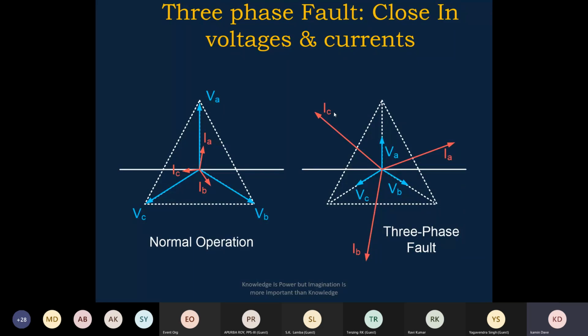Negative and zero sequence is less than 20%, and phase current is higher than 1.2 times or 1.5 times, and the voltage is less than this, then it is considered a fault condition, not a load condition. So that is called three-phase fault condition identification. Three-phase loop has to be calculated. So that is how the three-phase loop will be calculated in that case.